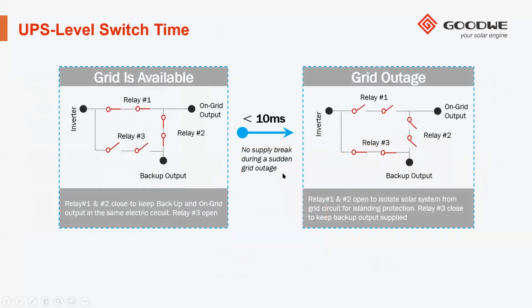So all of our hybrid inverters have UPS level switch time. We have double isolated relays, so relay 1 and 2. Within 10 milliseconds, our relay switch and switch in relay 3 to run the backup output. Our inverters also have an option under advanced settings that I'll show you a little bit later for grid quality detection. Should one disable that, you unfortunately will no longer have the 10 milliseconds changeover time because the grid will no longer be actively monitored.